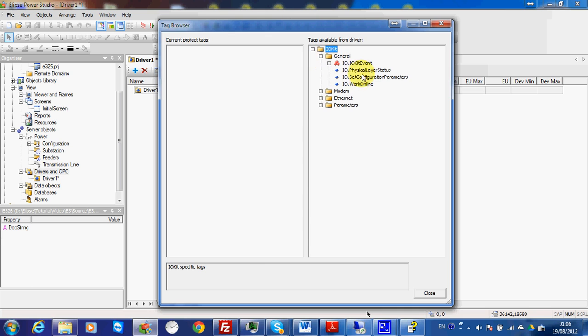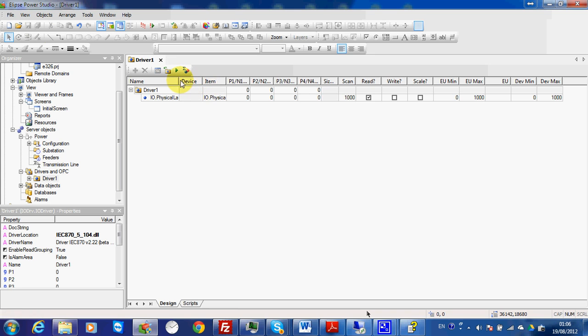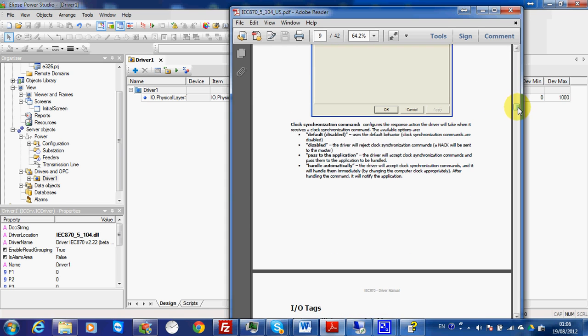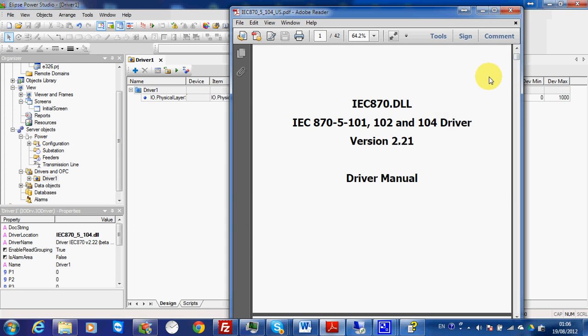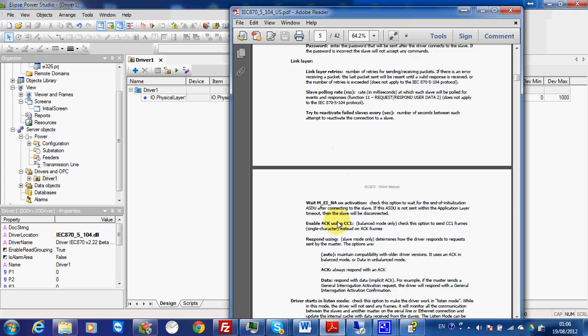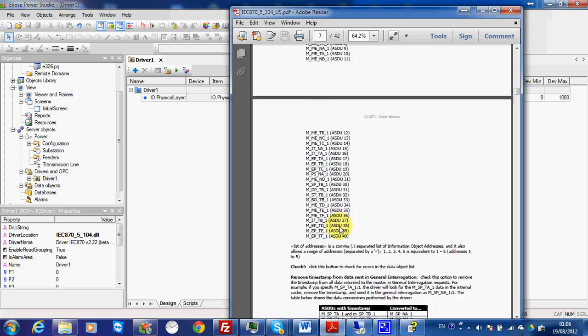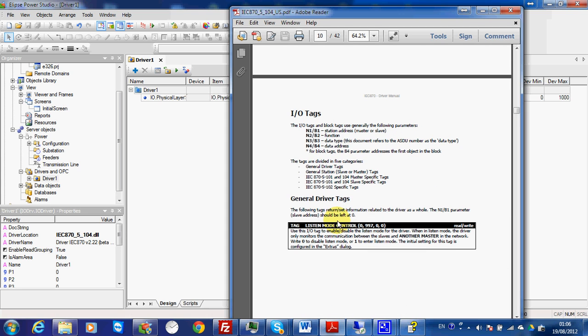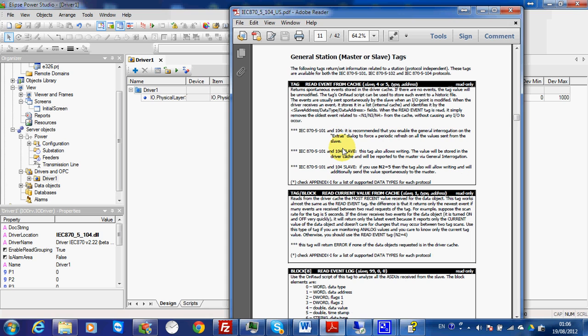In IOKit I can choose the physical layer to check if the two drivers can communicate. I can also check the documentation, which for the IEC 104 driver has very useful information. For example, I can check the parameters: N1 is the station address, N2 is the function, N3 is the data type, and N4 is the data address.